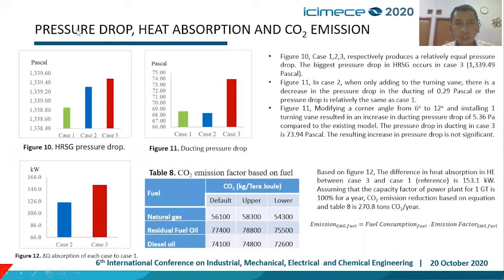Pressure drop, heat absorption, and carbon dioxide emission. From figure 10, case 1, case 2, and case 3 respectively produce a relatively equal pressure drop. The biggest pressure drop in the HRSG occurred in case 3, 1,339.49 Pascal. From figure 11, in case 2, when only adding the turning vane, there is a decrease in pressure drop in the ducting. The 0.29 Pascal pressure drop is relatively the same as case 1.